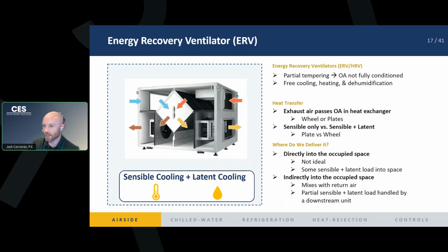We don't have to have a DX coil. We don't need a compressor. You're simply passing the air over each other in order to capture or recover that heat, right? And so there are energy recovery ventilators, ERVs. Those can be wheels or plates. Essentially, the air mixes in different ways depending on how much latent or sensible heat you want to do. If you do a wheel, you're going to get both because some of the air actually ends up touching each other and the moisture can cross between the streams. But if you only want to do sensible transfer, you can keep those air streams completely separate with a non-permeable plate, right? And these two streams will just pass over each other without touching. And the only heat transfer is sensible, right? You don't get any moisture that passes between the two streams. It's just the sensible dry bulb temperature change.